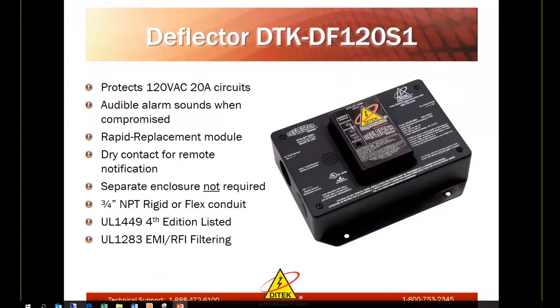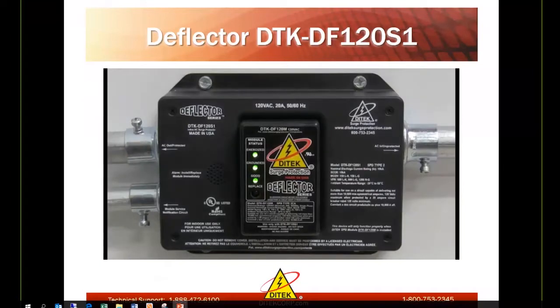And separate enclosures are not required for this device. You can see the mounting holes on the flange. It does take 3/4 NPT rigid or flex conduit, and it is UL listed 4th edition. And it does also have a UL 1283 noise filtering listing through UL for electromagnetic interference as well as radio frequency interference. There's another close-up picture of it, and that's it wired in to the circuit.